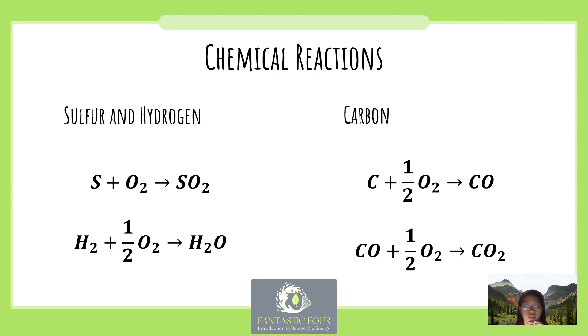Nearly all sulfur burns into sulfur dioxide (SO₂) and nearly all hydrogen burns into H₂O. Carbon is burned and forms either carbon monoxide (CO) or carbon dioxide (CO₂). Carbon monoxide can form when there is insufficient oxygen during combustion, or even in the presence of stoichiometric or excess oxygen due to incomplete mixing and short combustion time. Combustion of coal produces pollutant emissions including unburned carbon, carbon monoxide, unburned hydrocarbons, sulfur dioxide, ash, and nitrogen-oxygen compounds. These effects on the environment were discussed in the previous section.